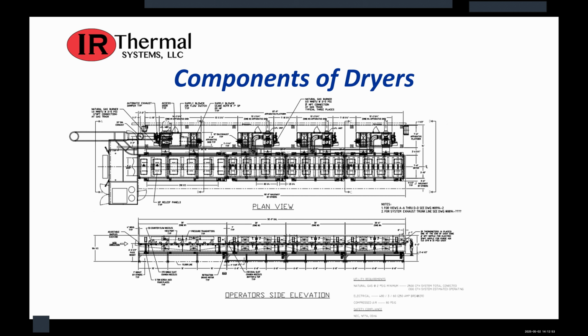The big thing about developing a maintenance plan is scheduling your downtime. There will be downtime on every single system. In order to keep it to a minimum, you want to schedule when it's going to be, because the worst case scenario is it happens at 1 in the morning when you have a component break. There comes your downtime. So in looking at this example, we had a 4-zone drying system where they had 2 different drying profiles within that drying system. The first zone on the left had a counterflow nozzle over a flotation airfoil, while zones 2 through 4 had flotation nozzles.